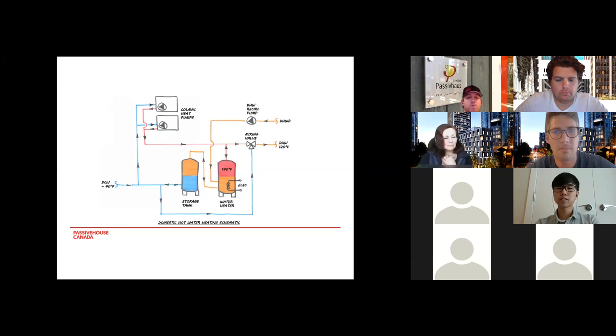Secondly, when the domestic hot water heat pumps—the Colmac units—and the recirc pump were not in operation, I'd expect the water inside the tanks to naturally stratify. This means the hottest water would migrate to the outlet of the secondary storage tank, or electric water heater, and the coolest water would be located at the inlet of the first storage tank.